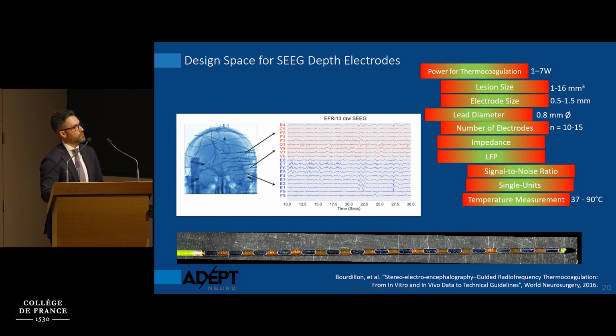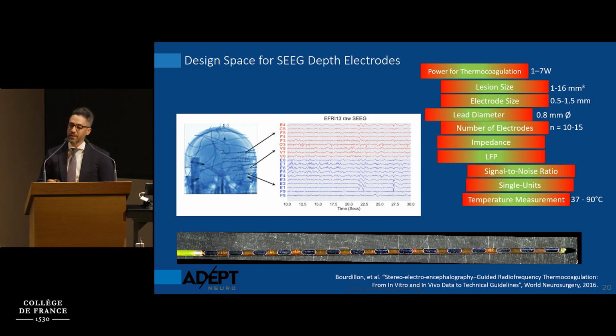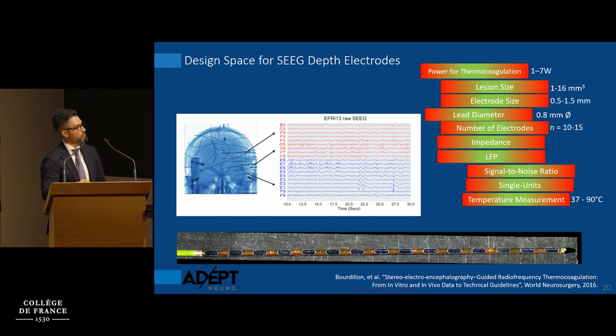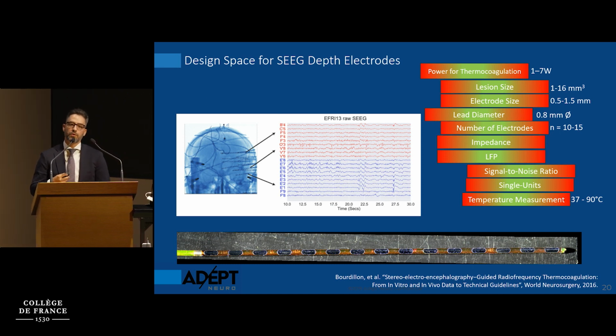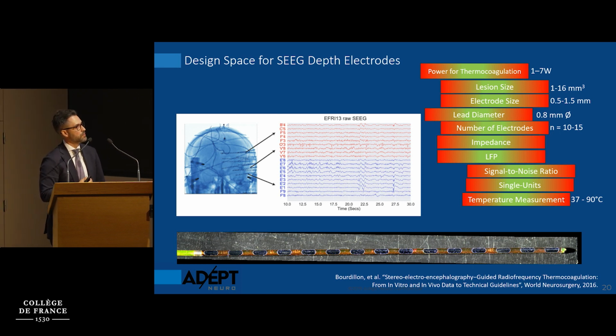And then the diameter, I showed you 1.3 millimeters before for DBS. Here we were at 0.8. So when the engineers found this one out, a lot of the Aleva engineers were working on this device, as you can see. When they found that one out, they were like, that's impossible, less than a millimeter, but they got there. They got there and they got 15 contacts on there. There's the impedance. So you want a certain impedance that allows you to record from the brain, but then you need an impedance that allows you to thermocoagulate or ablate the brain without moving this device. And so those are two opposing forces, the impedance required for recording and the impedance required for thermocoagulation.